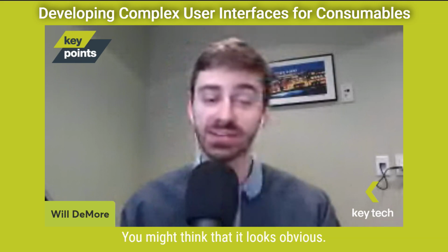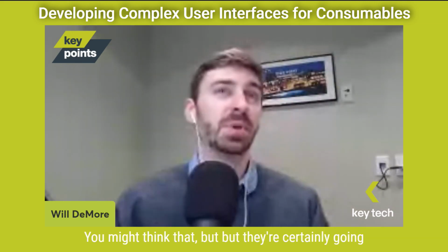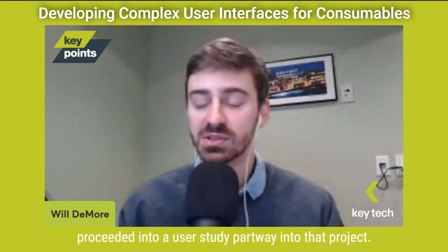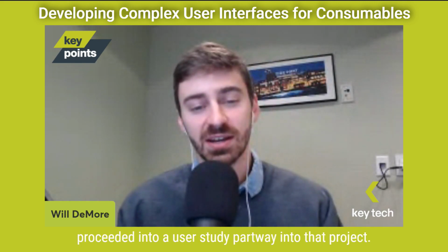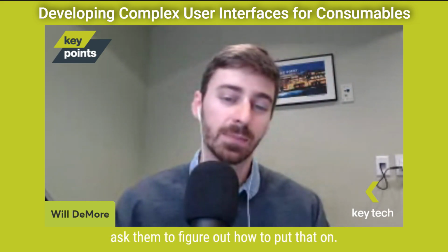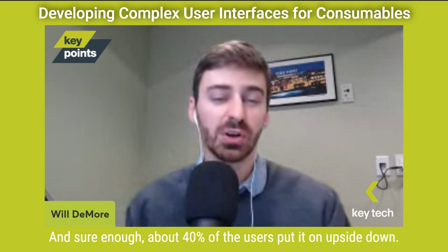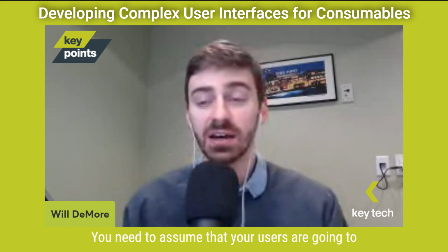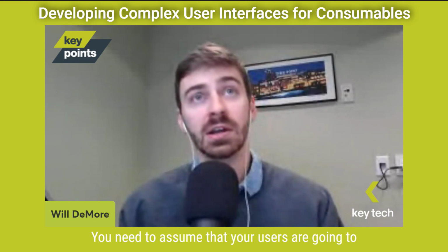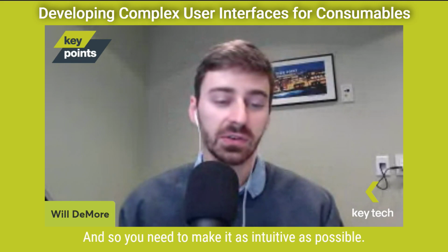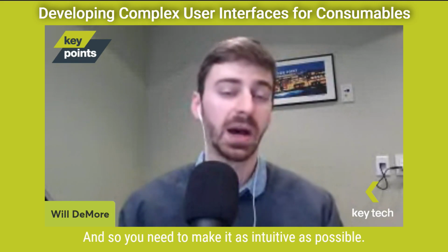You might think that it looks obvious. You might think that, but they're certainly going to put it on upside down. And sure enough, we proceeded into a user study partway into that project, and put this mask in front of people, asked them to figure out how to put that on. And sure enough, about 40% of the users put it on upside down. You need to assume that your users are going to do all sorts of wild things to misuse your device. And so you need to make it as intuitive as possible.